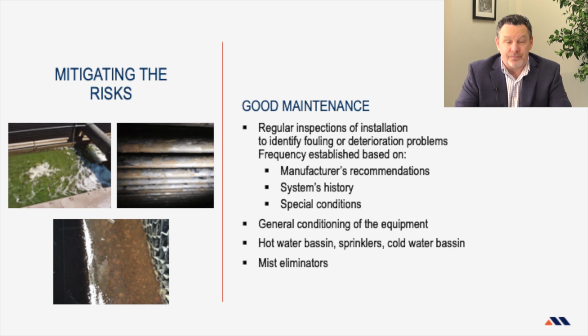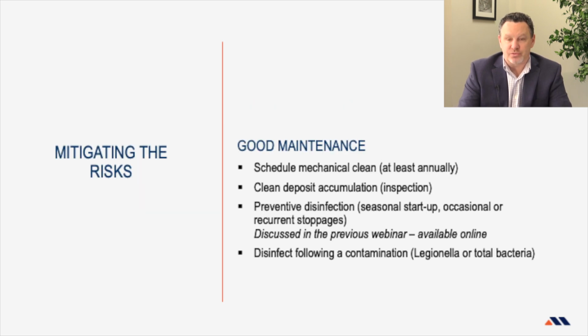Inspect the cooling tower. Go upstairs, go outside if it's on the roof. Have your maintenance people go and inspect, make sure things are looking like they're supposed to, that water's not being overflowed onto the roof, or that the spray nozzle or distribution channels are clean. Those are all real important things to do at a basic level to mitigate these risks.